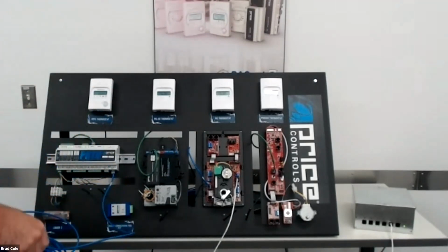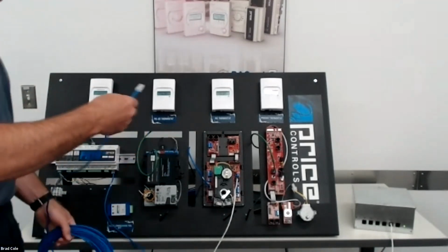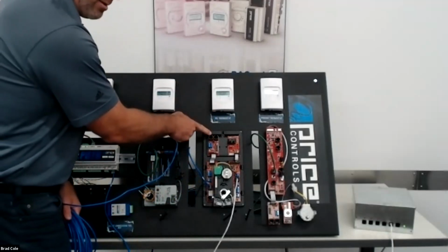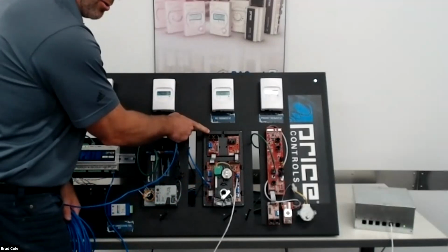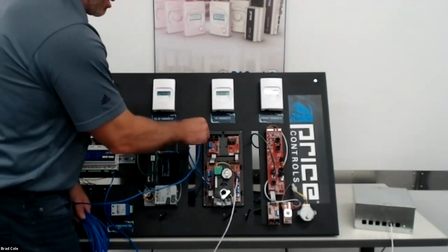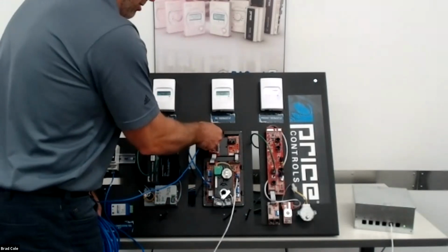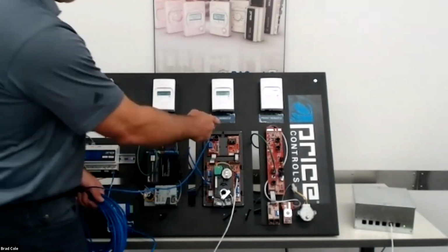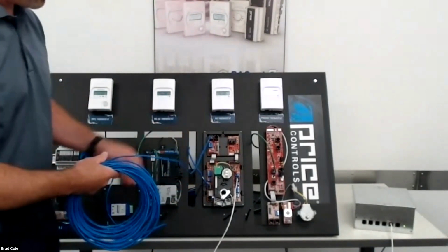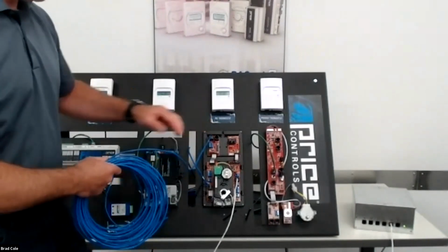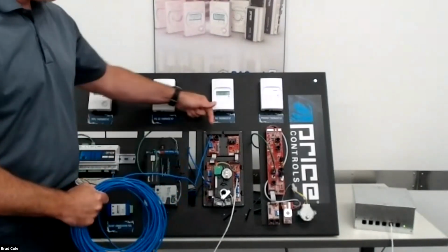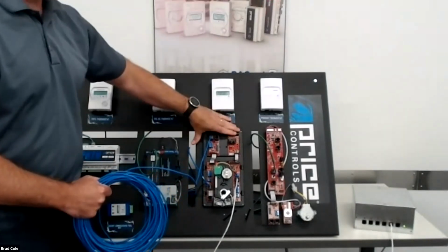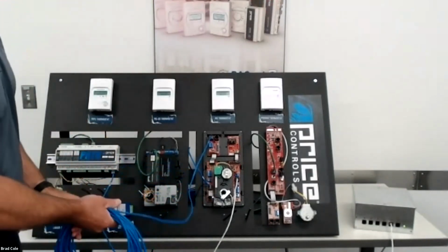And then all you're going to do, once I get this guy out here, is plug them in. It might be tough to see here, but it's in all our manuals, and it was in the presentation. You're just going to plug it into the RJ45 jack on the BACnet card. Immediately as you start doing that, plug him in, now you have some communication indication for receive and transmit, and this thing's going to start to try to talk to this PIC controller. You would then take the next 35-foot cable, plug them into the jack beside, and start to daisy chain up to 30 PIC controllers or Prodigy controllers on your BACnet network.